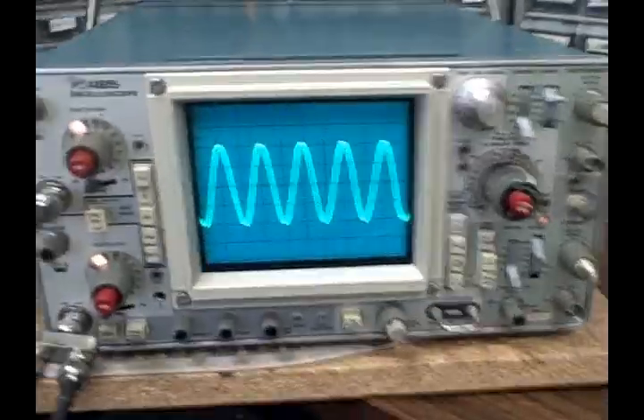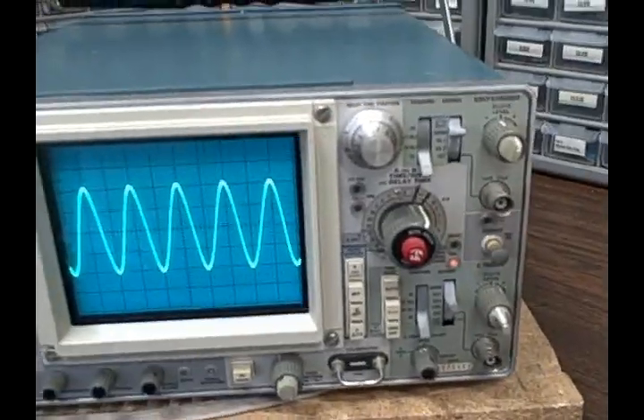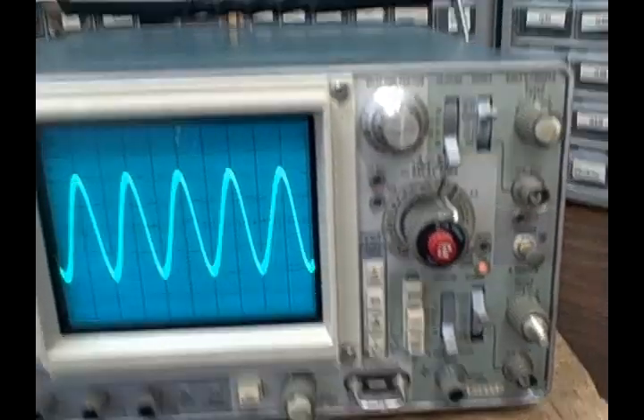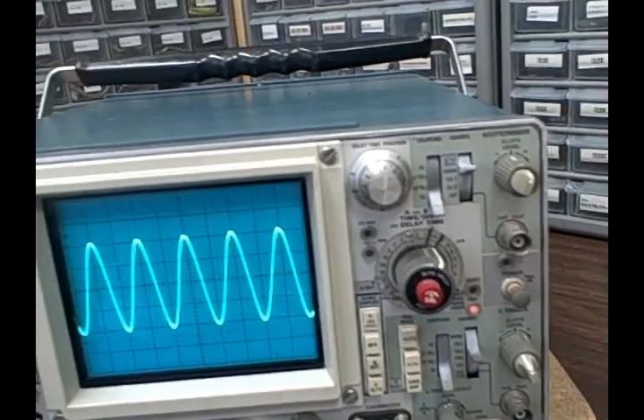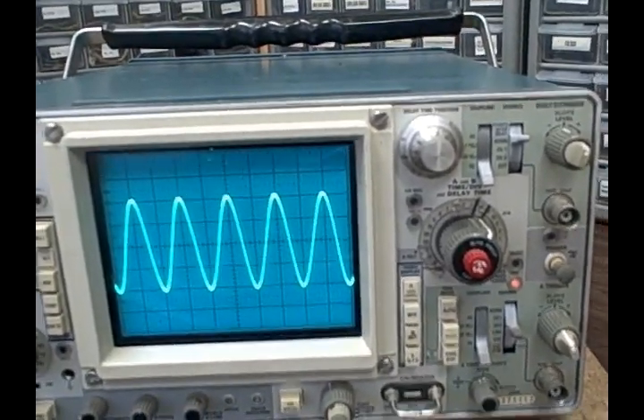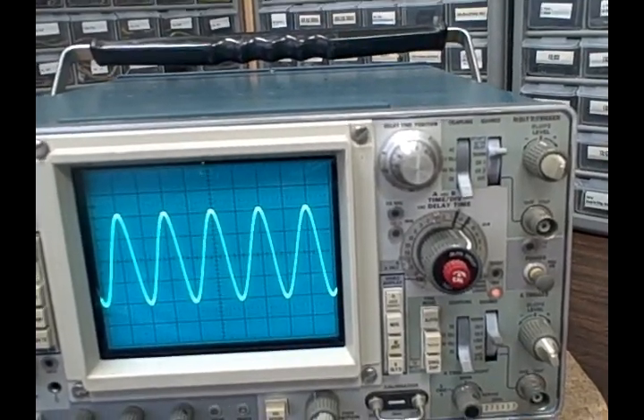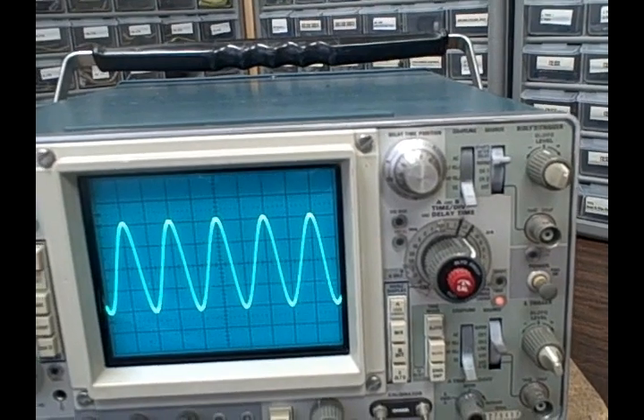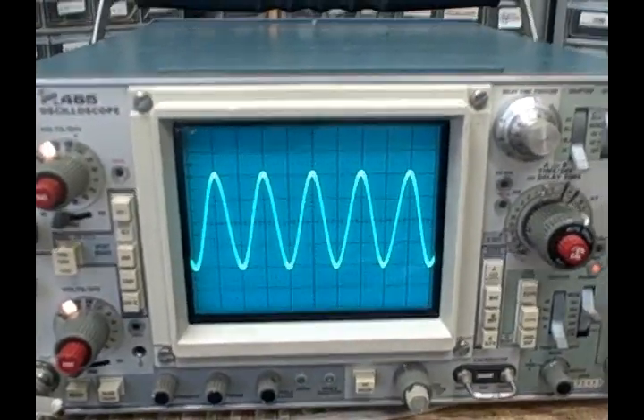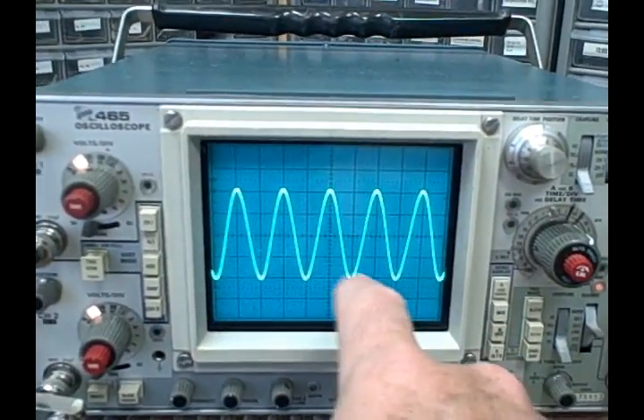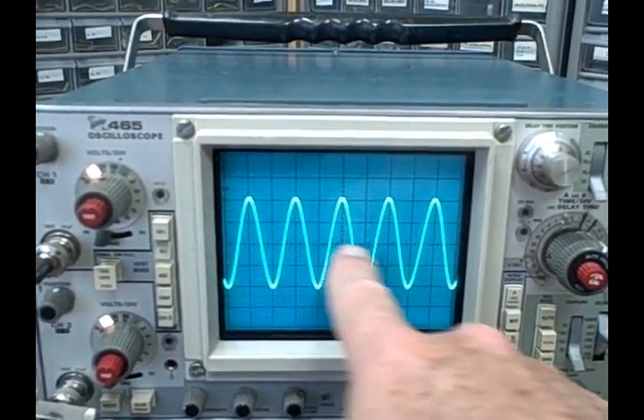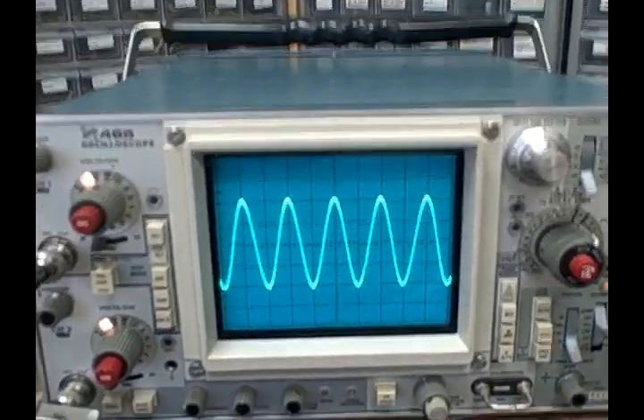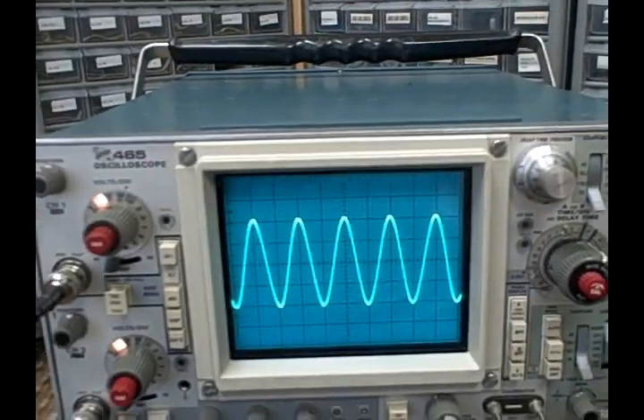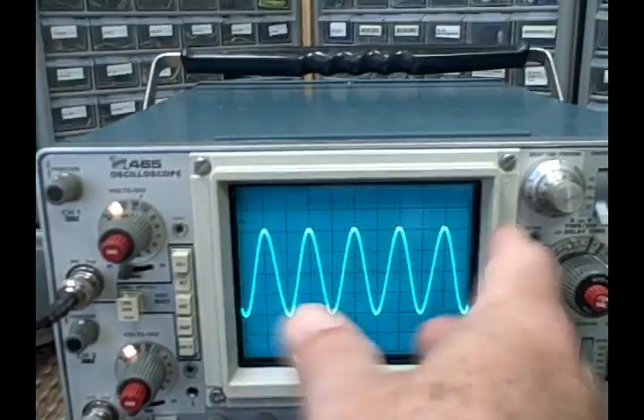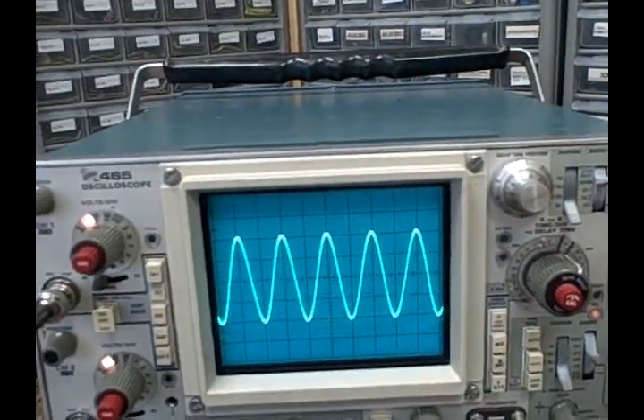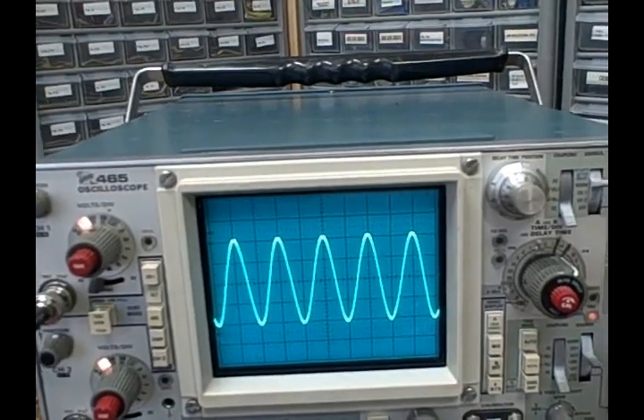All right, so now let's take a look at the horizontal. Now this thing has 2 horizontal time bases, which is a good thing. You've got the standard time base A, which you'll use every day. And then you've got a second time base with a time delay involved on B. And the idea is you can use the second time base and time delay to zero in on any portion of a signal on the screen and then magnify it so that you can see more detail without leaving the position that you're on and disturbing the first few cycles that you decide to let through.